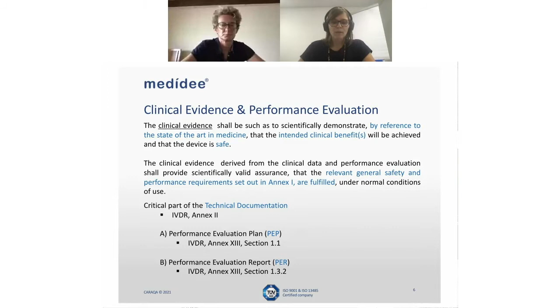So what is performance evaluation for an IVD medical device? It is composed, as illustrated here, of 4 different pieces, like a puzzle that fits together: first it addresses the scientific validity, the analytical performance of the device, the clinical performance, and then it also takes into consideration the post-market performance follow-up activities performed on the device itself.